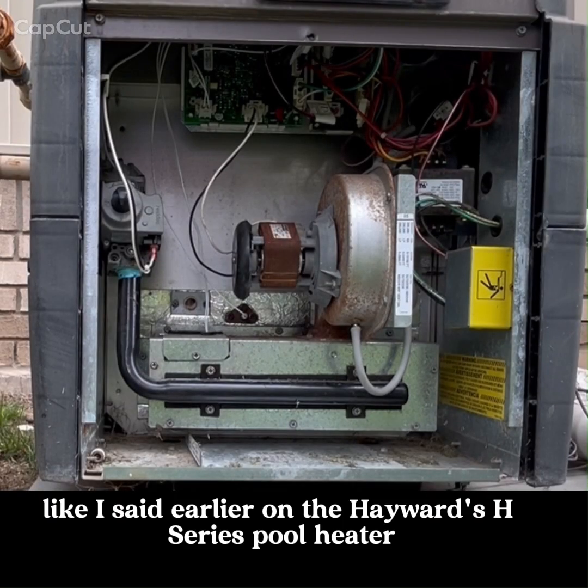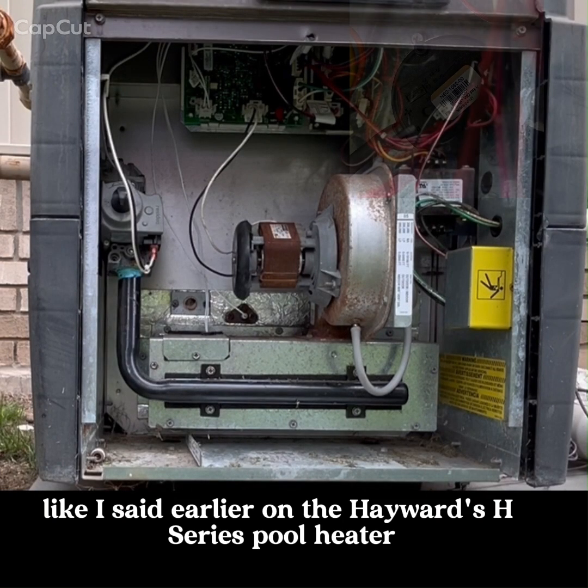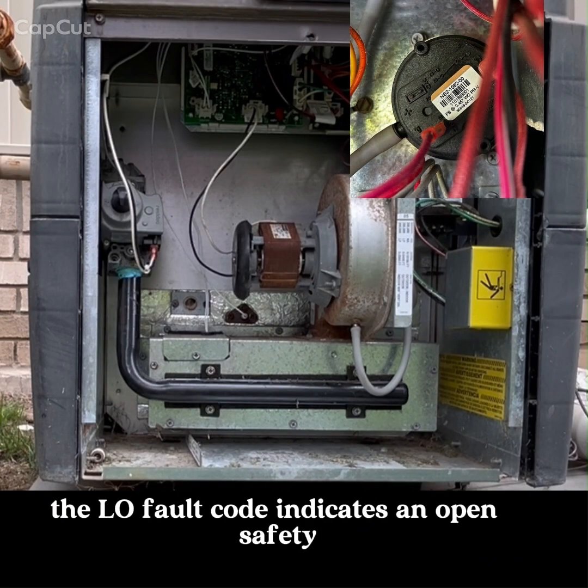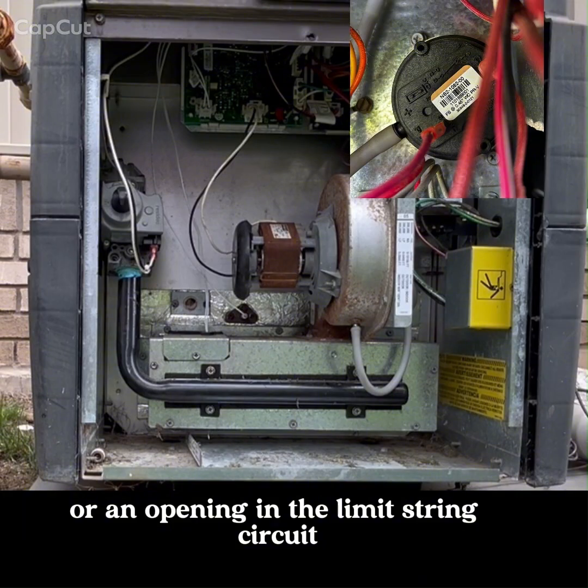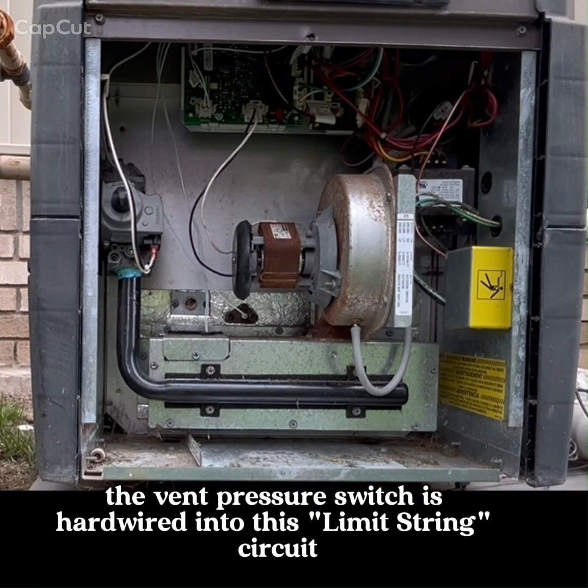Like I said earlier, on the Hayward H series pool heater, the LO fault code indicates an open safety or an opening in the limit string circuit. The vent pressure switch is hardwired into this limit string circuit.